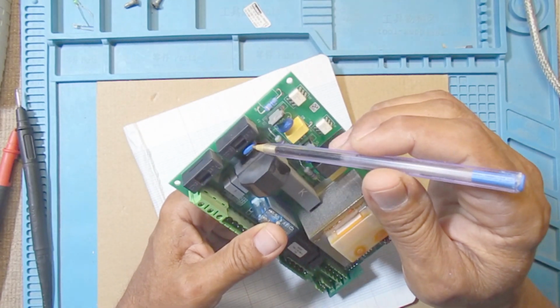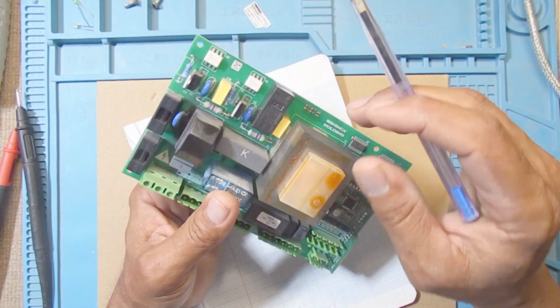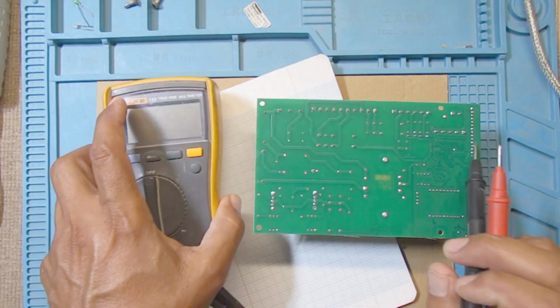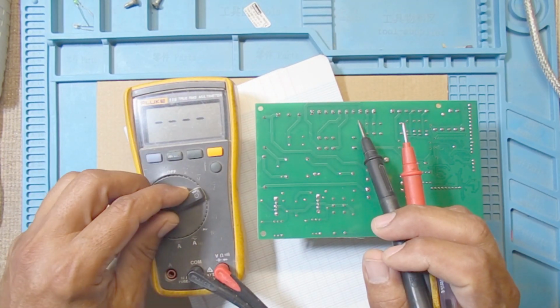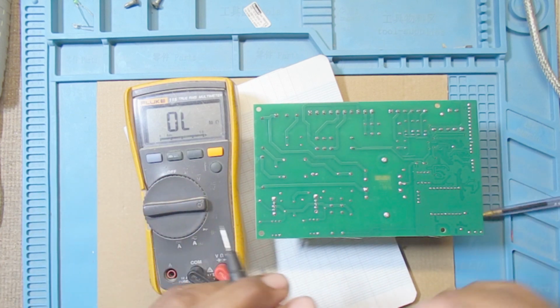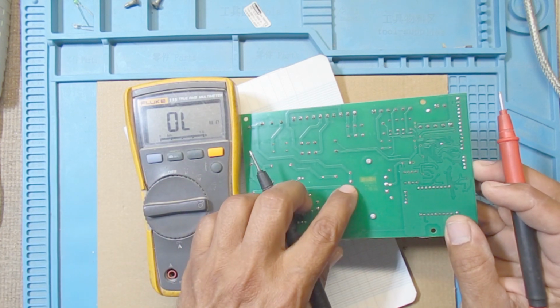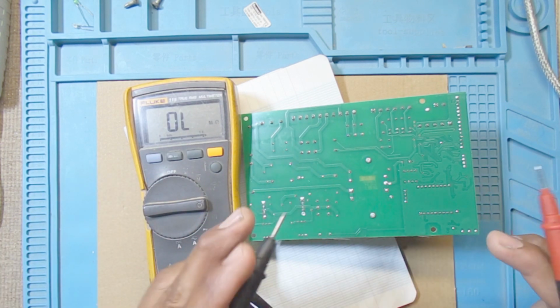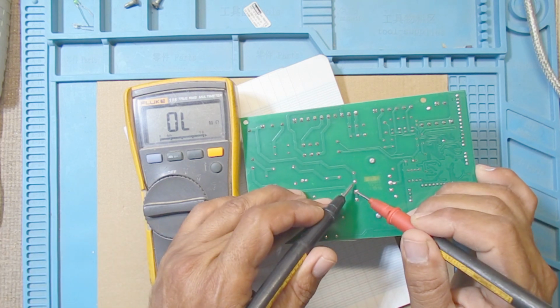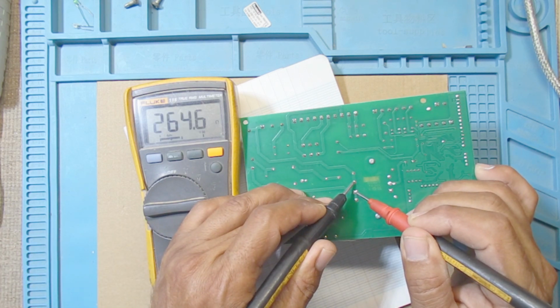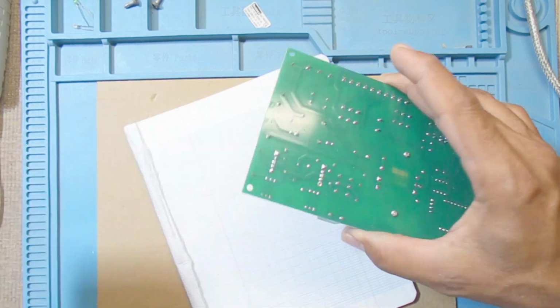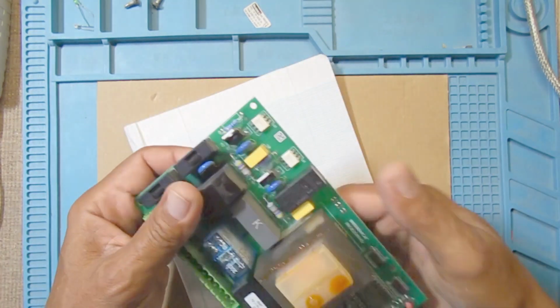Before replacing the varistor, I will check the transformer using the meter to check the resistance of the winding. Here we have the primary side, and here we have the secondary side. So we have 264 ohm. The transformer was saved by the varistor.